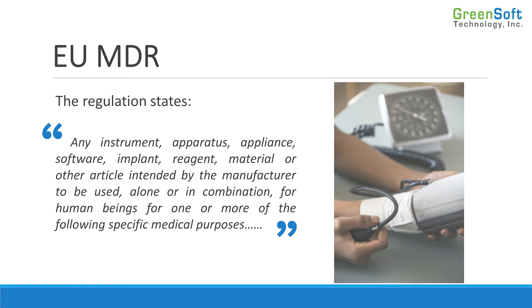Looking back at this, a couple of things I want to point out: it says any instrument, apparatus, appliance, software — notice software is on this list. So what that means is that if we create an app, an iPhone app, that helps us figure out what's causing our headache — we enter in our information, it gives us a risk analysis of our health — anything like that, that software is now a medical device. So you're going to have to incorporate that into the medical device regulation processing.